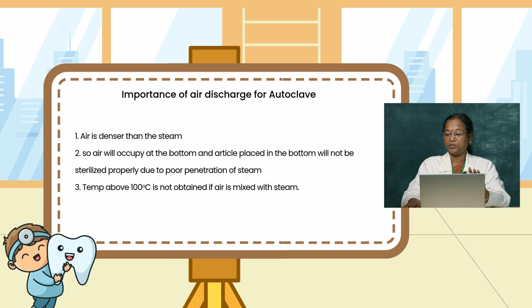And another thing is, when air is mixed with the steam, the penetration is affected. We always say moist heat, the steam, is highly penetrative. That is hindered when air is present. So, very important. Approximately you can keep it open for 5 to 10 minutes. After you switch on, you see if there is hot steam escaping, then you can close the outlet. That is mainly for discharging the air. That's a very important point you should note down for an autoclave.